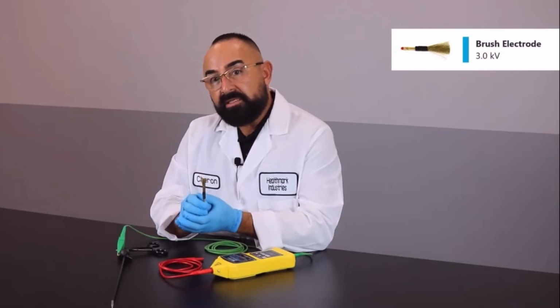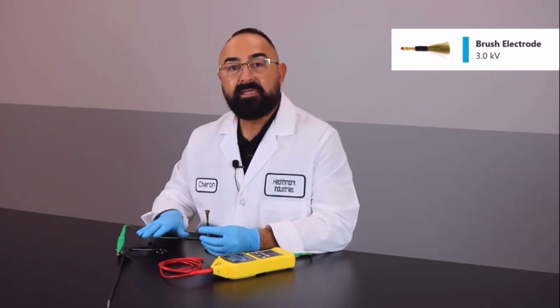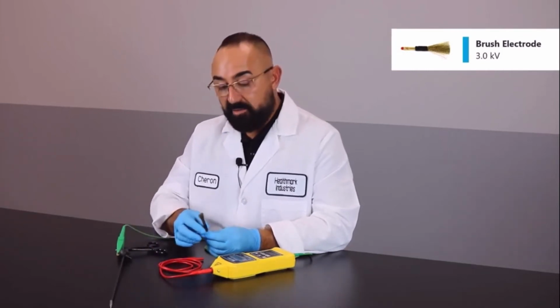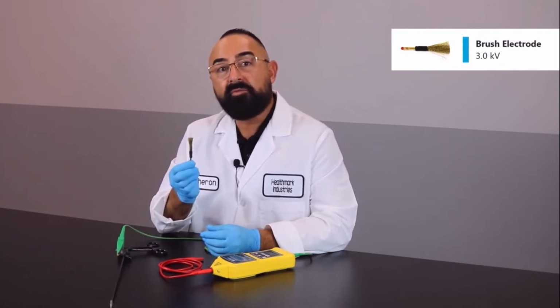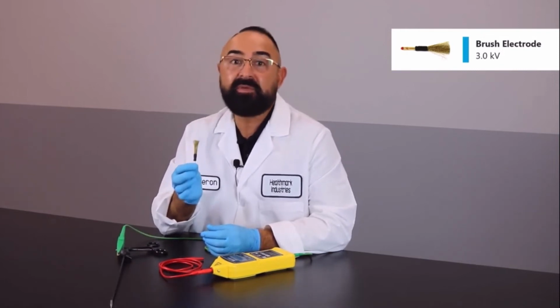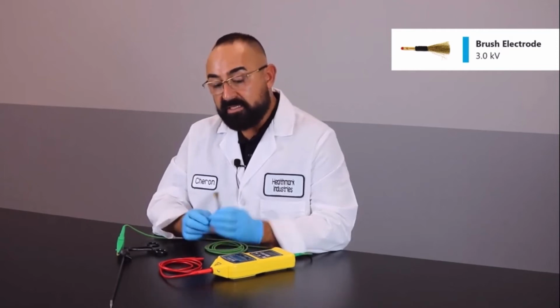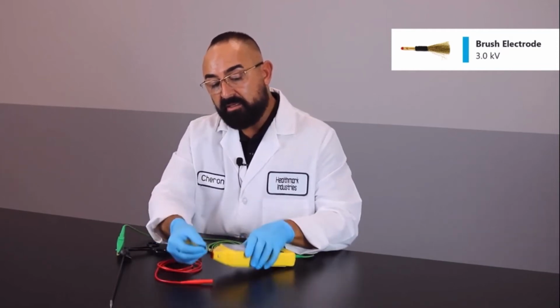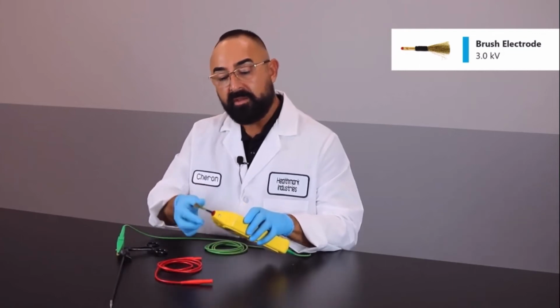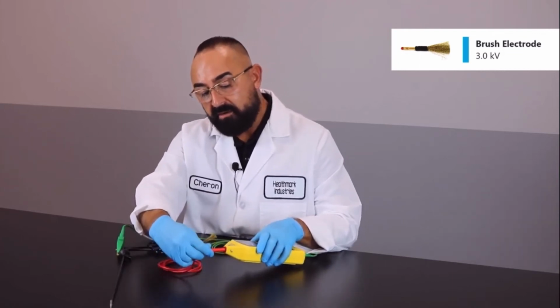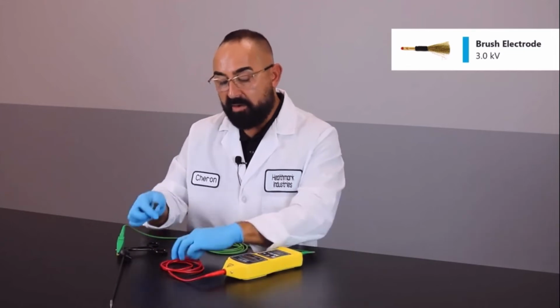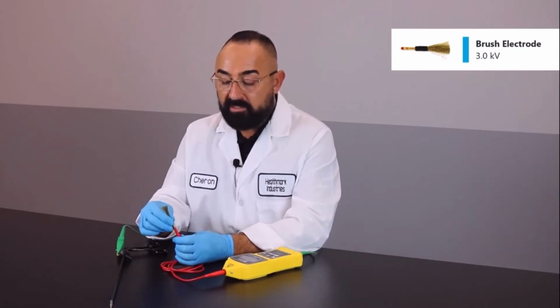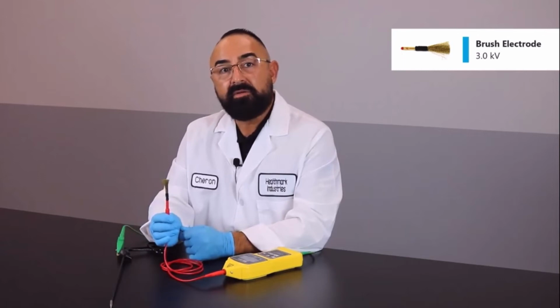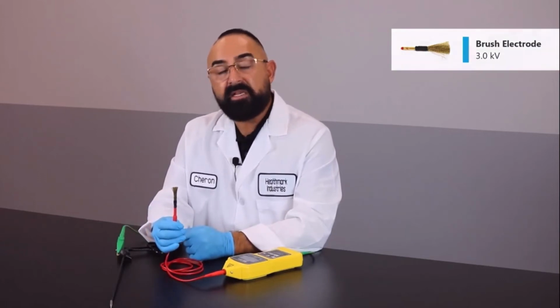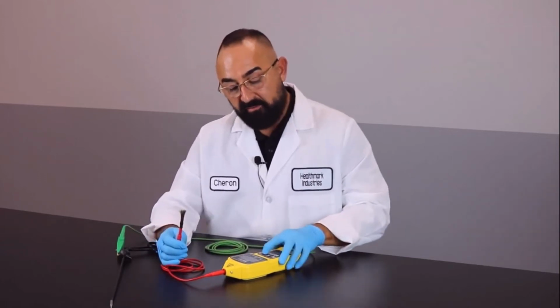This accessory is called the brush electrode. We're going to be using it today to specifically test an insulated handle on a laparoscopic instrument. You will see throughout the tutorial that it will be used in tandem with other accessories when testing. There's 2 different ways that this can be used. This can go directly into the unit itself, like so, or using your red HV wire, you would connect the wire to the unit and the brush electrode to the wire. This specific accessory is set at a 3.0 voltage.